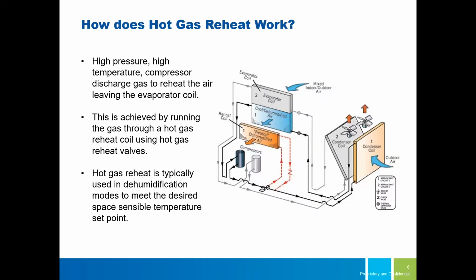That's why I wanted to use this basic picture to highlight that when you have hot gas reheat, you have 2 coils. It's not just one coil to do that work. And hot gas reheat is an indirectly temperature-based approach, because you're cooling the air and then reheating it, and as part of that, your dehumidification happens. Sorry about that. But that's the strategy for how you're trying to get to your space set point.